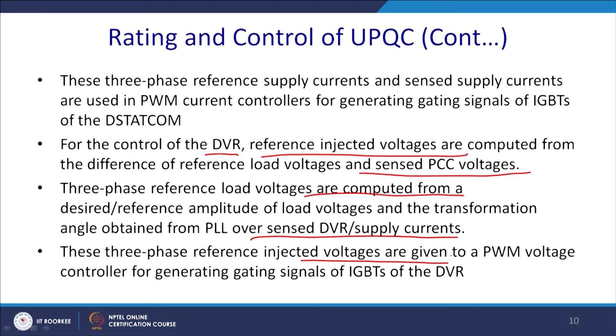this DVR part of the UPQC. For the control of this DVR, the reference injected voltage is computed from the difference of the reference load voltage and the sensed PCC voltage. This is required to be compared. The 3-phase reference load voltage is computed from a desired reference amplitude of the load voltage and the transformation angle obtained from the PLL over the sensed PCC supply voltages. These 3-phase reference injected voltages are given to the PWM voltage controller for generating the gating signals of the IGBTs of the DVR.